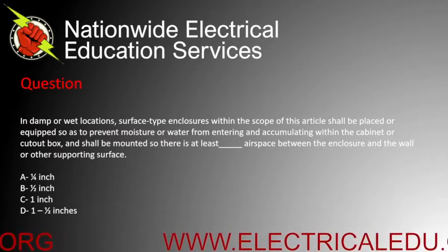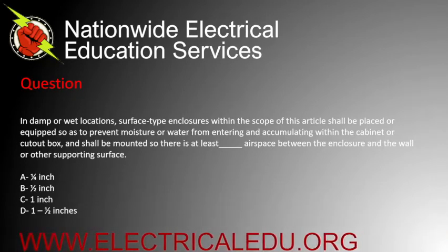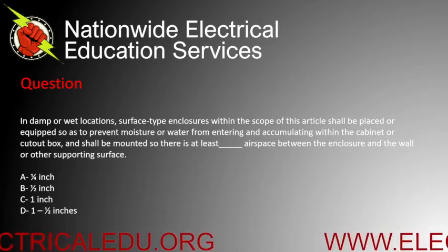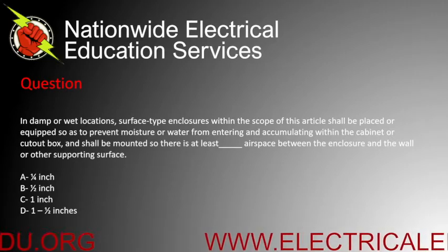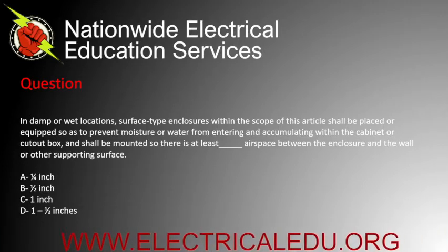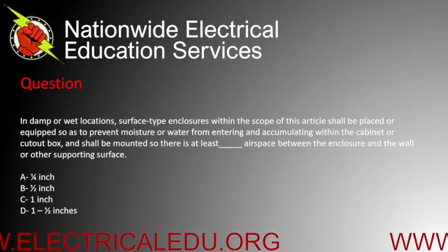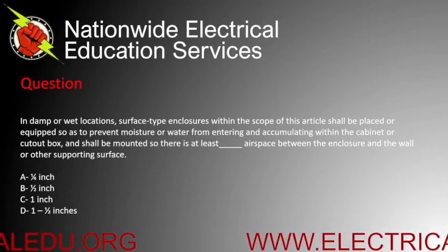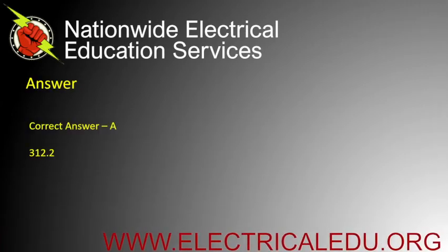In damp or wet locations, surface-type enclosures within the scope of this article shall be placed or equipped so as to prevent moisture or water from entering and accumulating within the cabinet or cutout box, and shall be mounted so there is at least blank airspace between the enclosure and the wall or other supporting surface. A) quarter inch, B) half inch, C) one inch, or D) one and a half inches. Correct answer is A.